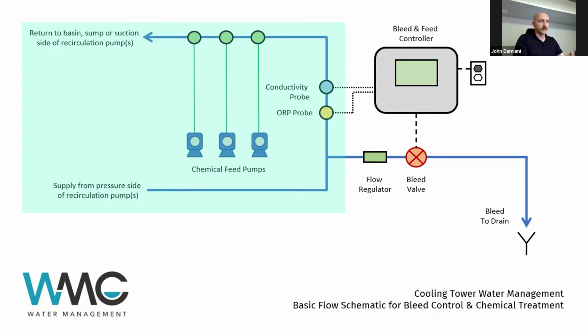And for any size system, it really doesn't matter what the size of this cooling tower might be. If this is a cooling tower, this could be 1,000 tons, 200 tons, 10,000 tons. Really, we just need a live sample. So this might only be a 3/4 inch line given any system. And in that line, we're just circulating. So we'll supply it from the pressure side of the recirc pumps, return back to the basin or into the suction side. And we've got a couple of sensors that are installed in there.